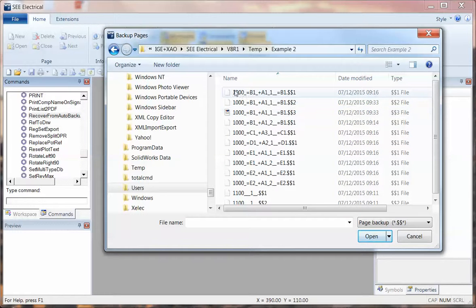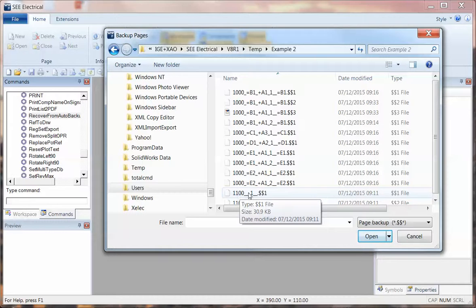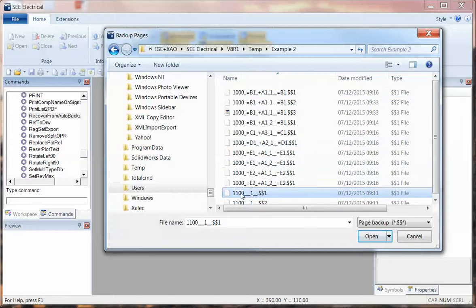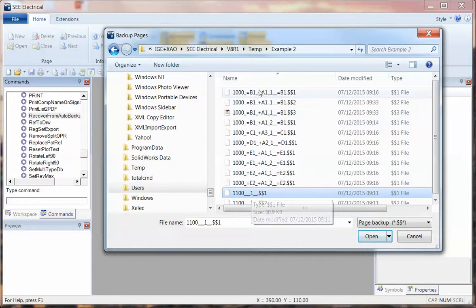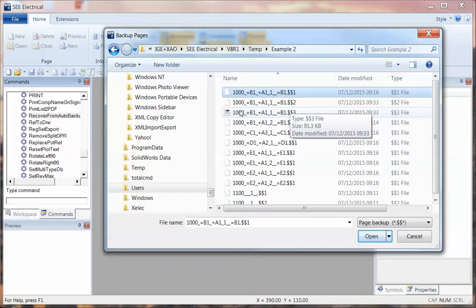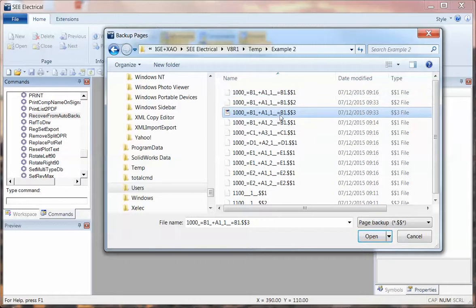Going back to the Public Documents folder, I'll find there's an Example Two folder in there. For each page, it's described by number: for IEC it's 1000, for IEE it's 1001, and for a panel layout or cabinet page it's 1100. That's the page type. You then have a series of underscores — if you don't use functional locations this one has no functional location, so you can see underscore underscore — then the page number, and finally dollar one, dollar two, and dollar three for the last versions of that same page.